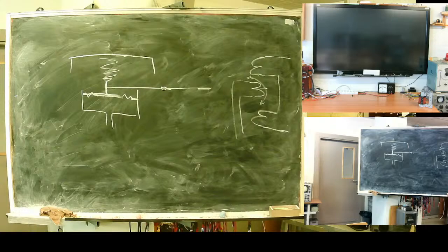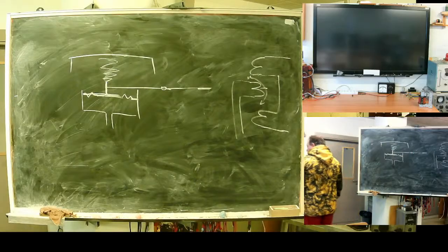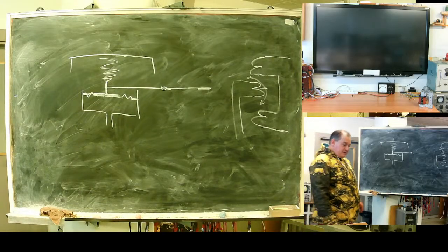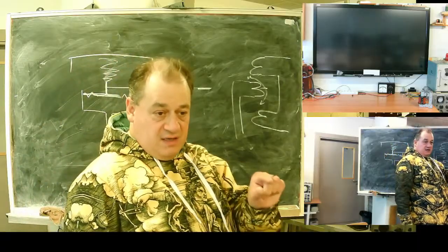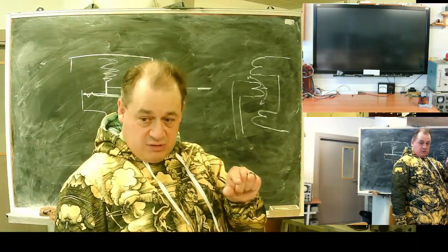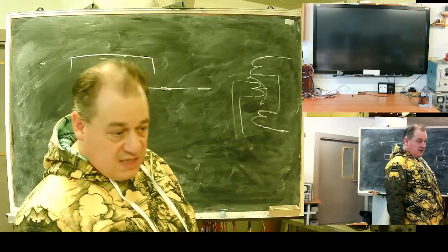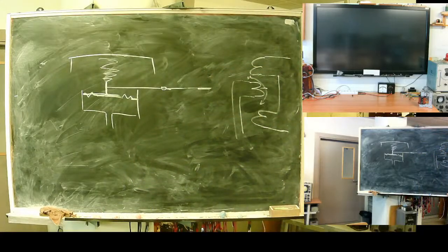There are elements whose resistance changes with temperature. Motor manufacturers plant them inside the winding; high-end models already come with thermal sensors as resistors inside windings. You only need to read resistance and set thresholds.